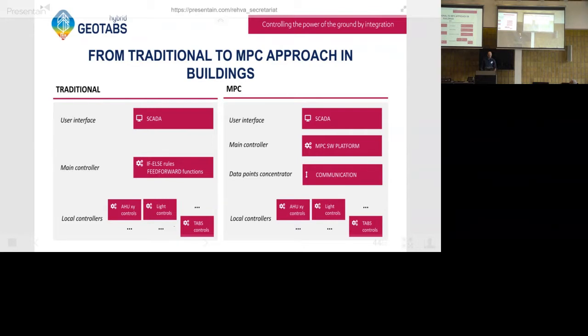Based on this, we can extend the control scheme with MPC in the following way: the main controller no longer contains if-else rules, but contains the optimization of the complete operation of the building, and the previously used main controller becomes only a data point concentrator, serving for communication between the MPC software, which is really software in the full sense of the word, and the subcontrollers. The rest of the system stays the same, so it's necessary to install this software in the building.